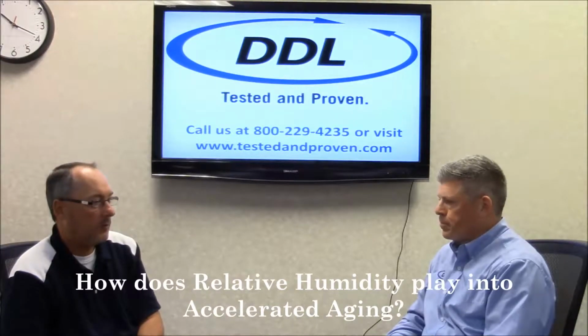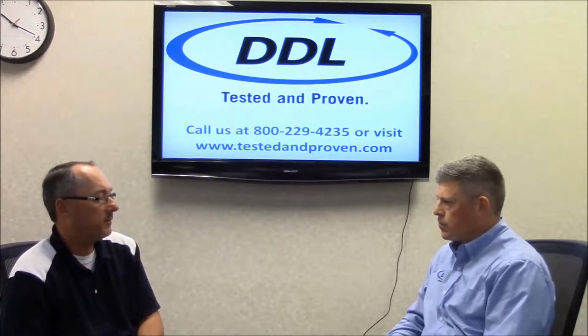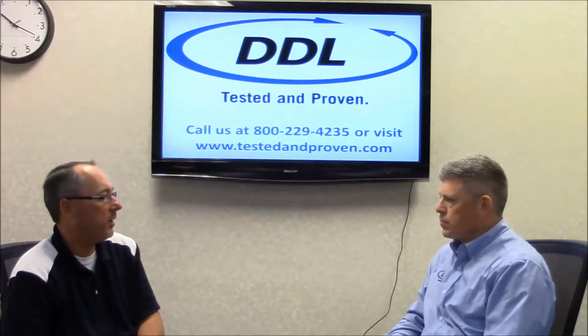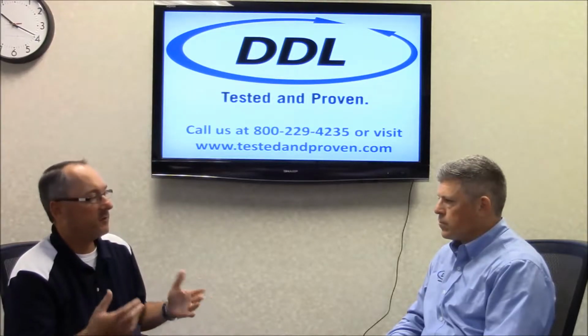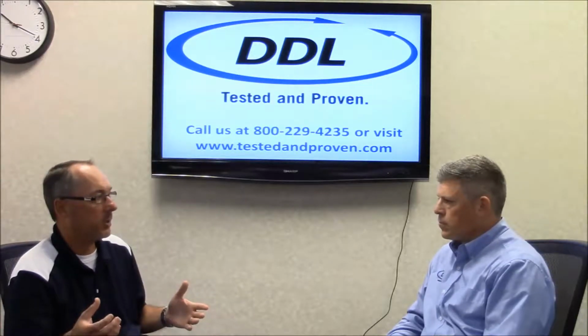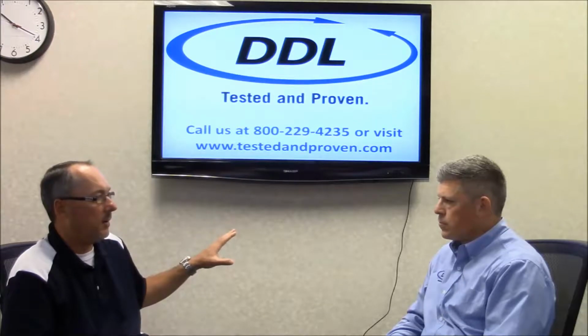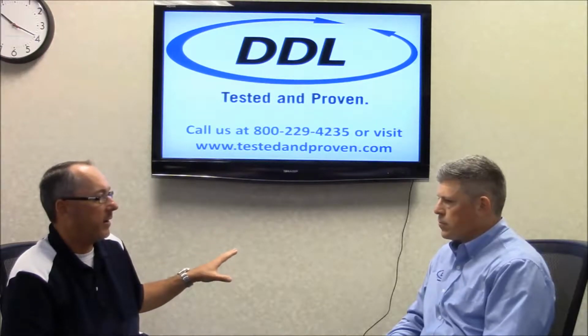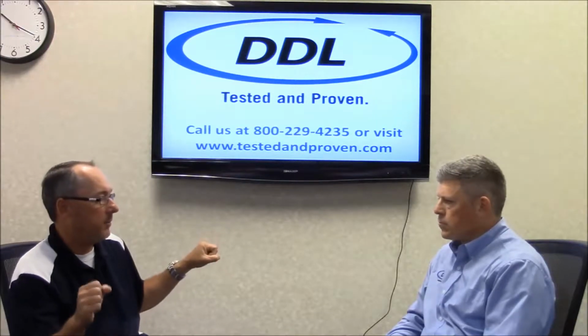Absolutely. It's probably one of the key questions that I get asked on a regular basis. What relative humidity should I utilize for my accelerated aging? And what everybody needs to understand is accelerated aging is all about time and temperature. Humidity really doesn't play a role in that Q10 factor. It's simply time and temperature.